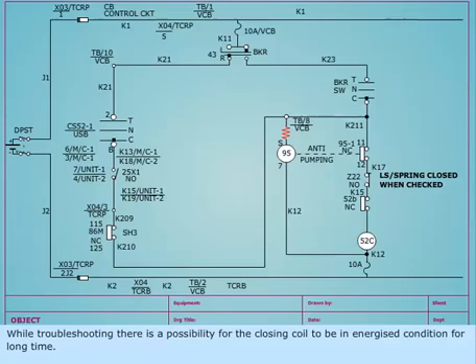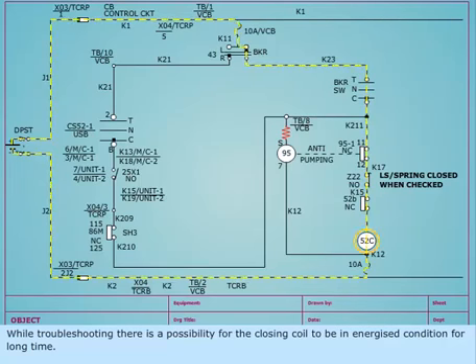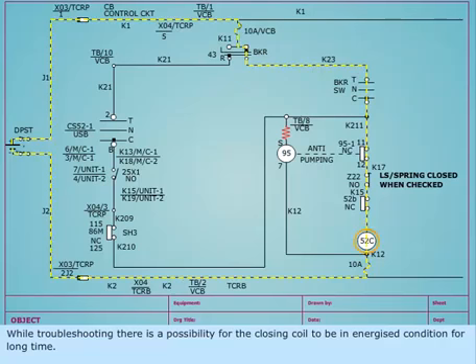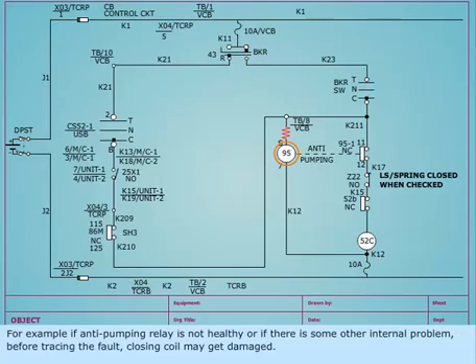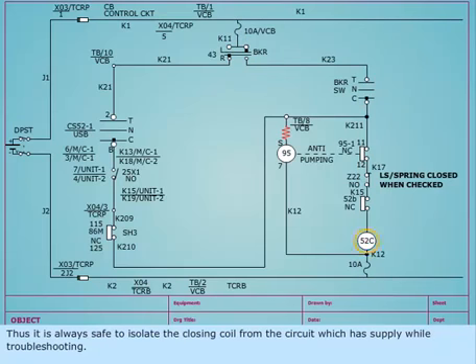While troubleshooting, there is a possibility for the closing coil to be in energized condition for long time. For example, if anti-pumping relay is not healthy or if there is some other internal problem before tracing the fault, closing coil may get damaged. Thus, it is always safe to isolate the closing coil from the circuit which has supply while troubleshooting.